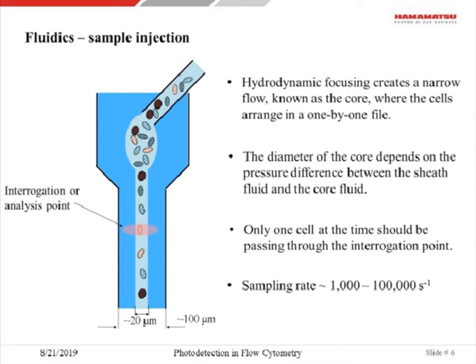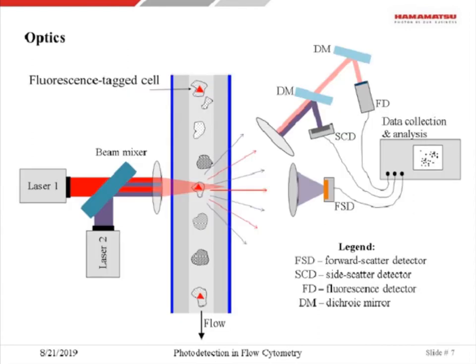At some point in the flow cell, there is a point known as the interrogation point. When a cell passes that interrogation point, light from an external laser illuminates the cell. Light scatters from the cell, and the scattered light carries information about the cell. In modern flow cytometry, the sampling rate of cells can vary from about 1,000 cells per second to, in some cases, even 100,000 cells per second.